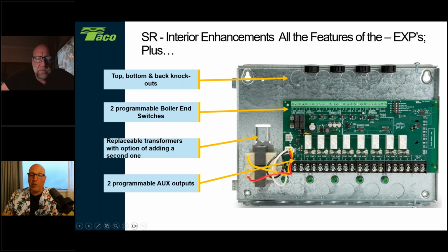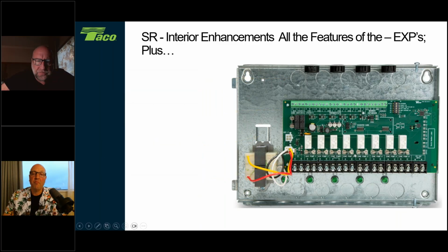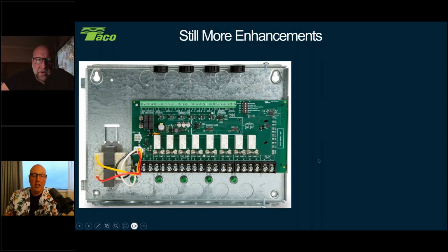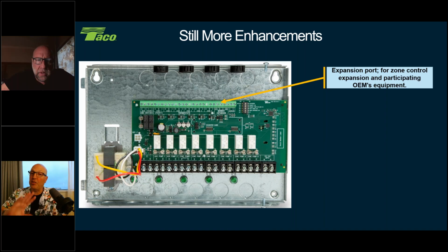And those auxiliary pump outputs: the switching relay has 2 auxiliary pump outputs. They do have default settings, but they are changeable. And again, we'll talk about that later. All right, a few more things that we have done to the switching relay. We still have that same expansion port where it can tie in up to 120 zones. It is also a terminal for some future growth where we might be able to start talking to other manufacturers, our OEMs, like boiler manufacturers, where we can have a little more two-way communication rather than just one-way communication.